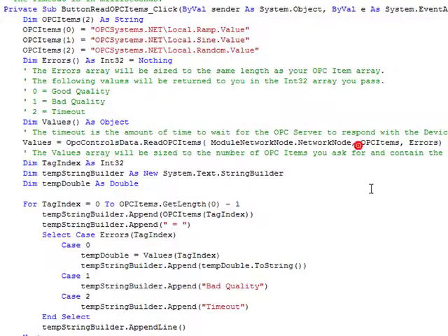The second argument is the OPC items themselves. Here we see an array of strings. We have 3 elements in this array, and here is the OPC server name, and then a backslash followed by the OPC item name. And that's how to specify the OPC items that you want to monitor from an OPC server. I do not recommend to put in a network node name here.